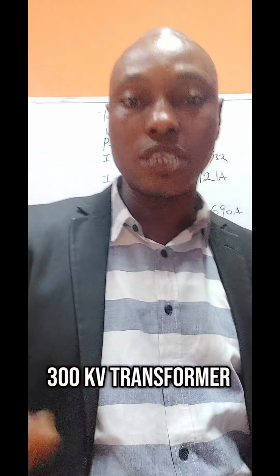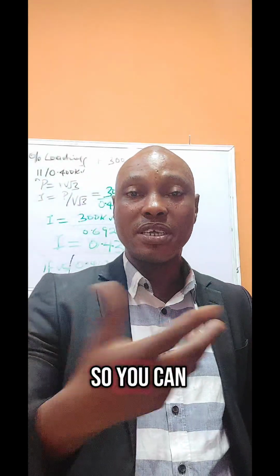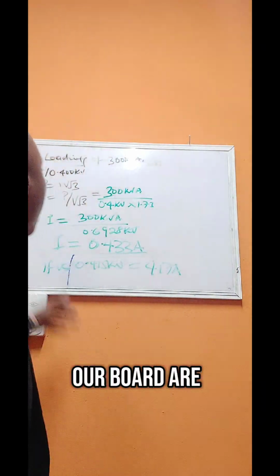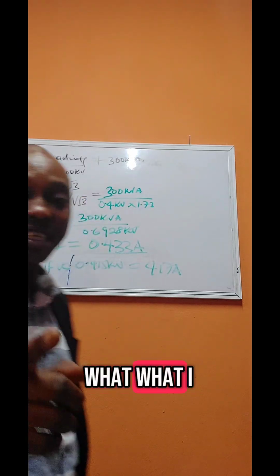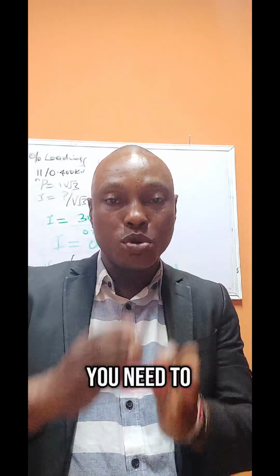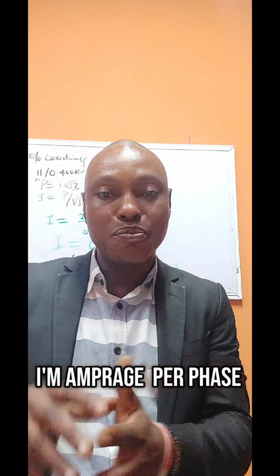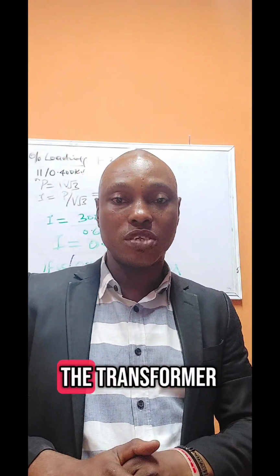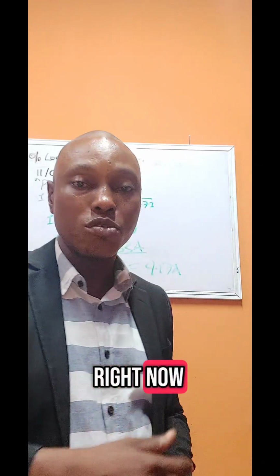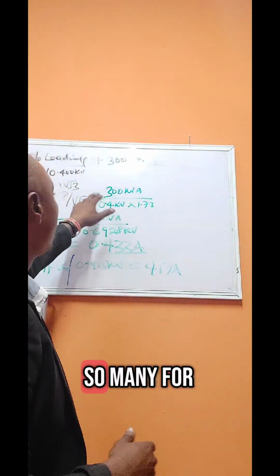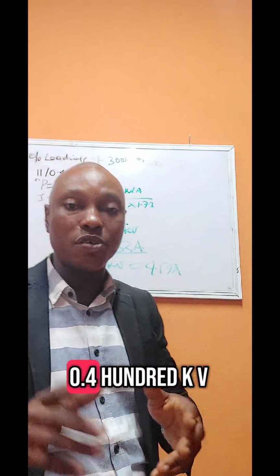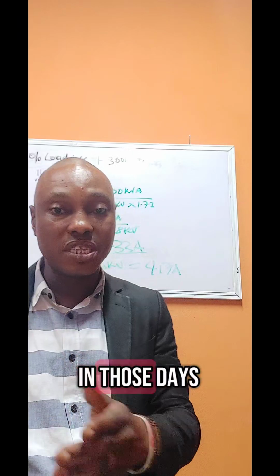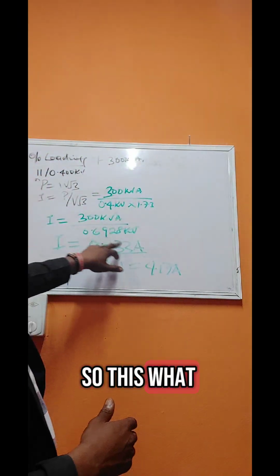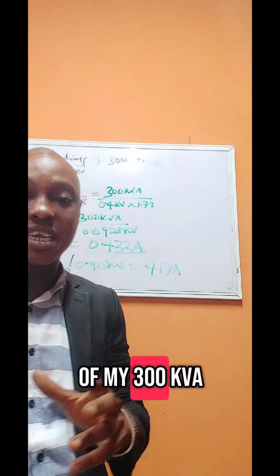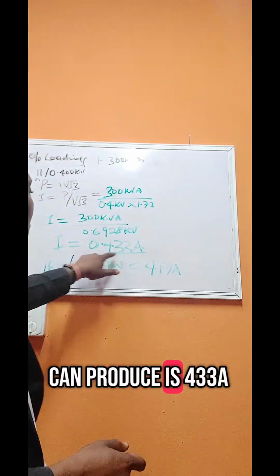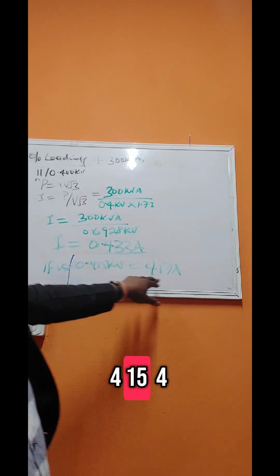Let me do the 300 kVA transformer, and then we move on. You can see the calculation for the 300 kVA on our board. Percentage loading, that we are still doing. But what I said earlier is, for you to calculate the percentage loading, you need to know the amperage per each phase of the transformer. So we have done 500. I'm doing 300 right now. For 300, to calculate, you still use the formula for fuse rating. So for 300 kVA, I use 0.400 kV, which is what we're using now. For 415 in those days, I still do that one too. So this is what it's giving me now. Per phase of my 300 kVA, the maximum it can produce is 433 amps, whereas if you use 415, it's going to give you 417.